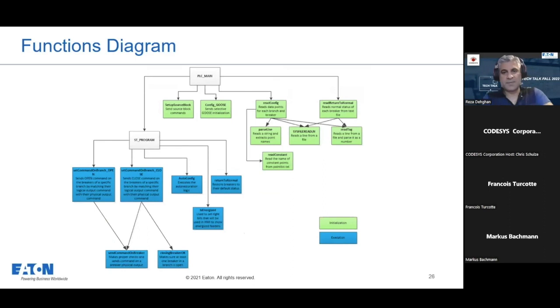Yeah, this is the functional diagram of the system. Again, not sure if we really need to dig into each of those functions, but you are all familiar with the whole structure of the CODESYS. Basically, we have a PLC main, which is the module that begins the process, the initialization phase. PLC main needs to execute some different codes that I already put here. These are different classes that I defined in my logic. Some of them read information from the text files, initialize the points that we need, and set up the initial status of the relays, exactly what we talked about, like selective GOOSE message or block source points for each of the relays.